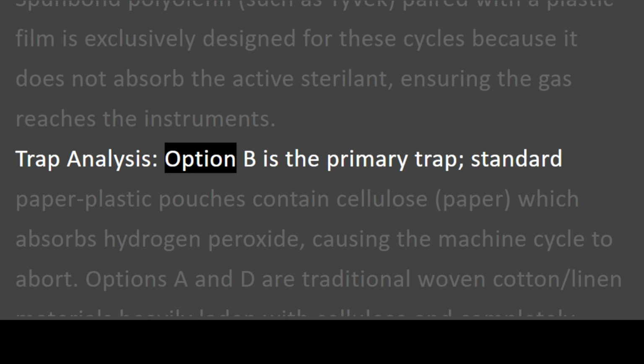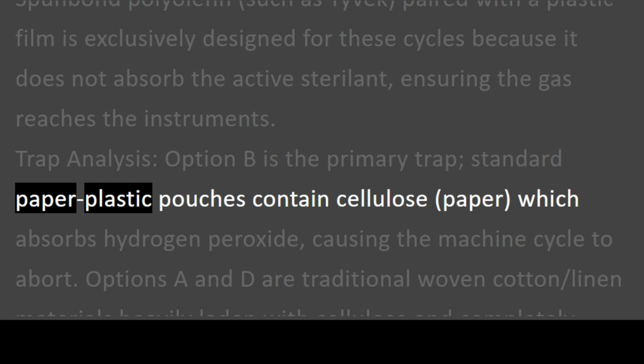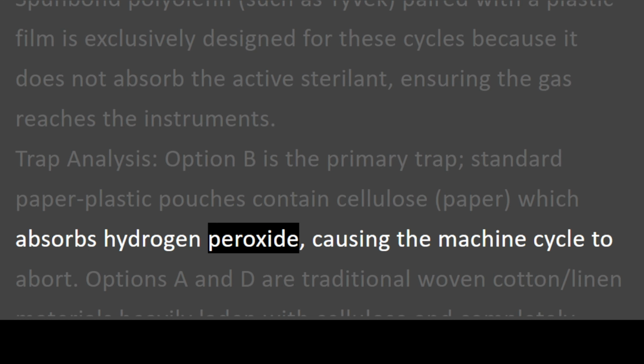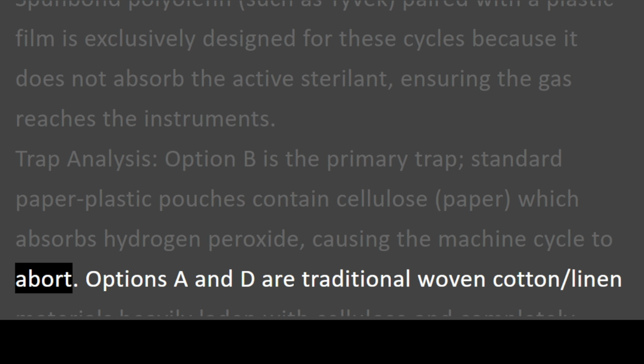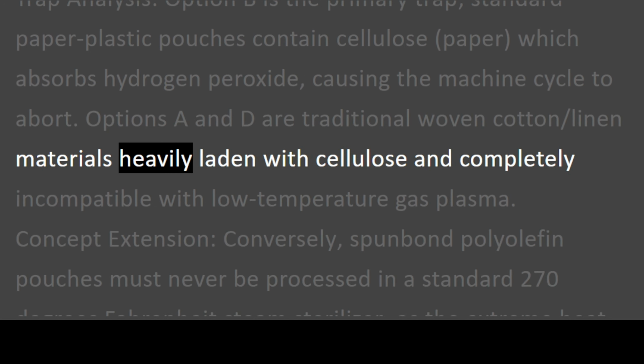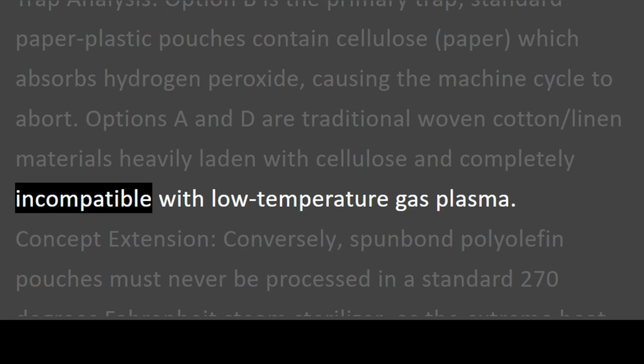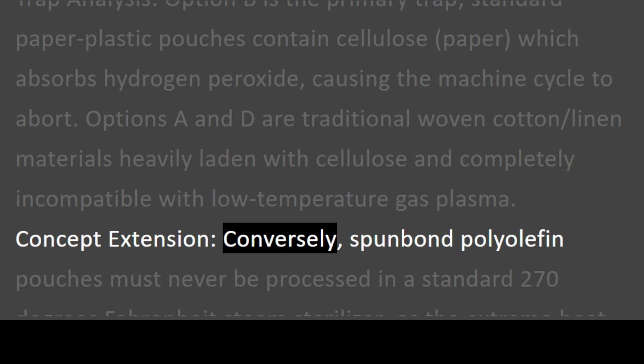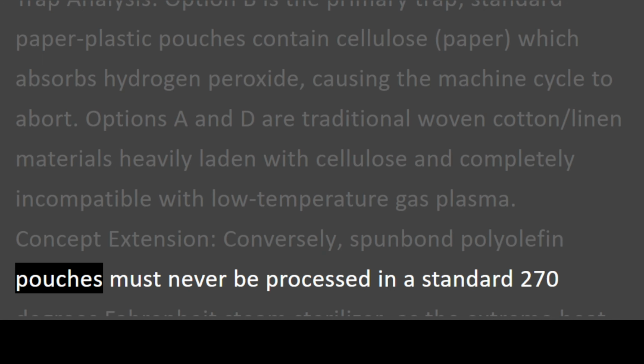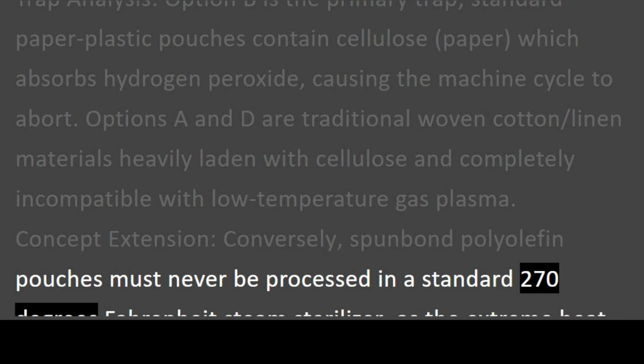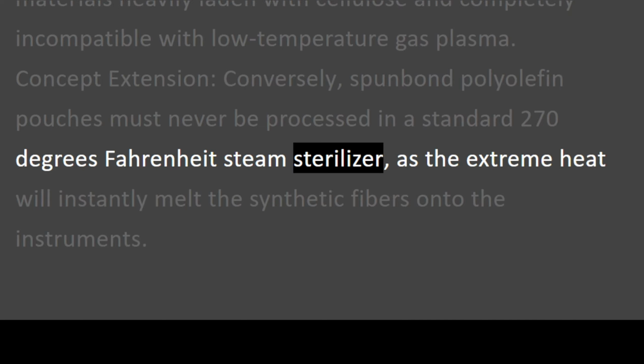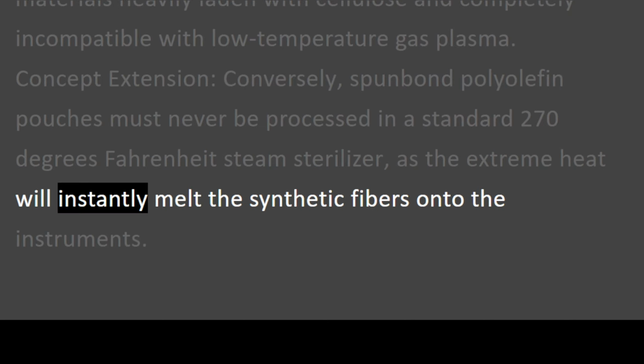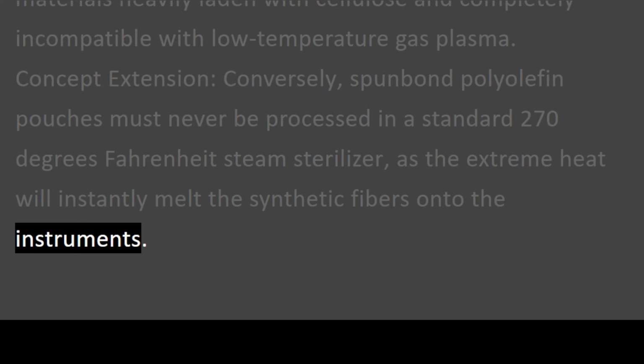Trap analysis. Option B is the primary trap. Standard paper plastic pouches contain cellulose paper, which absorbs hydrogen peroxide, causing the machine cycle to abort. Options A and D are traditional woven cotton/linen materials heavily laden with cellulose and completely incompatible with low-temperature gas plasma. Concept extension. Conversely, spunbond polyolefin pouches must never be processed in a standard 270 degrees Fahrenheit steam sterilizer, as the extreme heat will instantly melt the synthetic fibers onto the instruments.